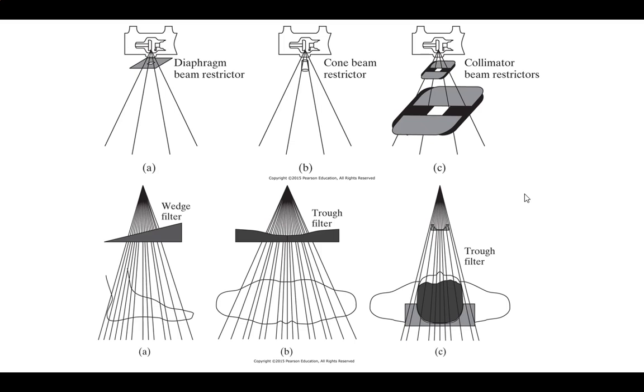A lot of them have collimators that are XY ones. They've got an aperture. You can think of it like margins on a page: you can set the left, right, top, and bottom. They're restricted very often because your films are going to be that size. And you'll see when they line you up, they'll have a light source with a mirror that they can switch inside, and they'll rotate so that actual visible light will go through the collimator.